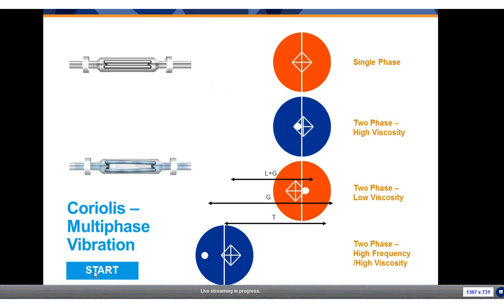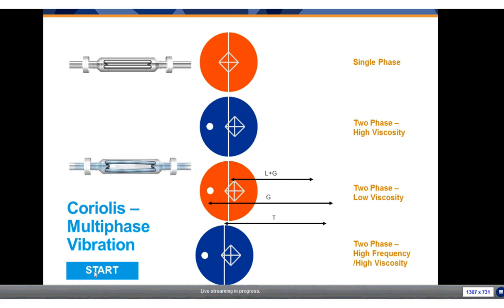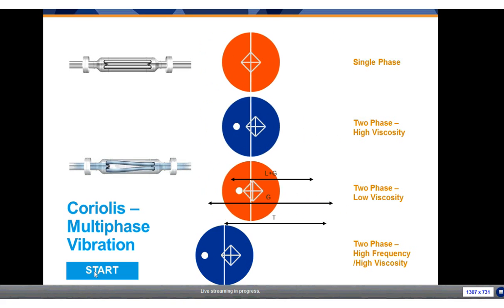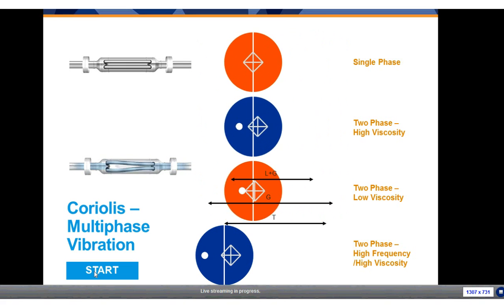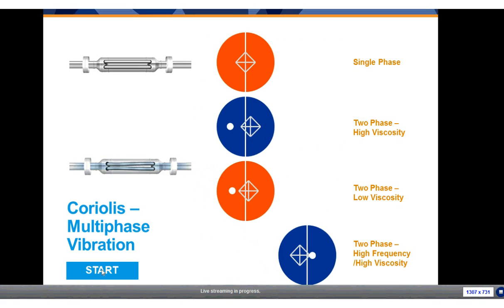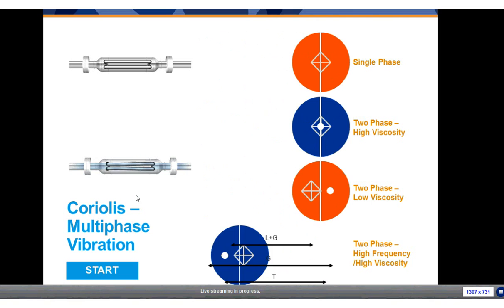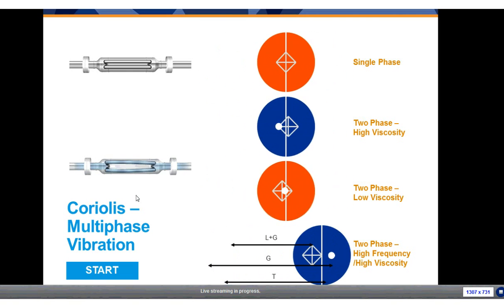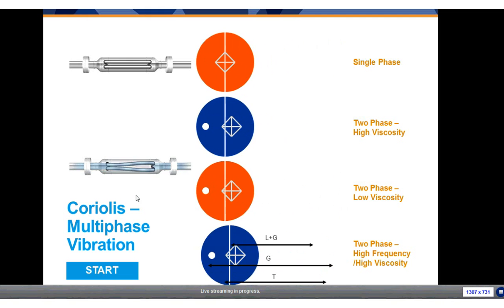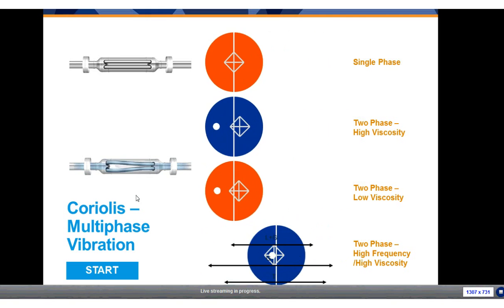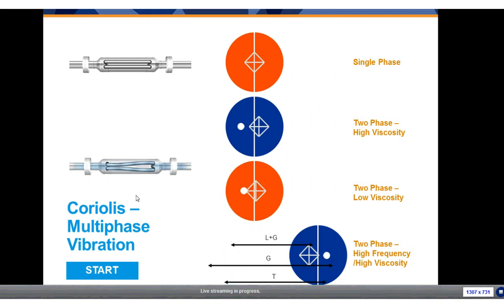With low drive frequency and low viscosity fluid, there is more gas bubble movement and some decoupling begins between liquid and gas. With high drive frequency, the air bubble moves rapidly back and forth, causing severe two-phase flow due to decoupling, and the center of gravity moves significantly. You can see the difference between high and low viscosity fluids in how the entrained gas bubble stays entrained versus decoupling.